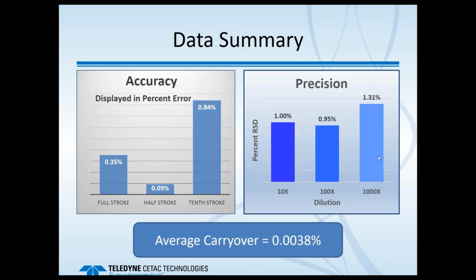So we did a number of tests, and I won't go through all the data here. But essentially the accuracy varies a little bit with the syringe depending on how much of the syringe stroke you use. It is most accurate somewhere between 30 and 100% of stroke. But even down at the 10th stroke, we're within 1% error. So the accuracy data there is displayed by percent error. And even at the 10th of a stroke, we're less than 1% error. So that's pretty excellent.